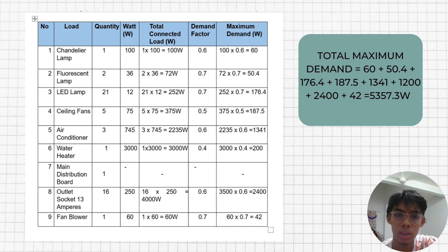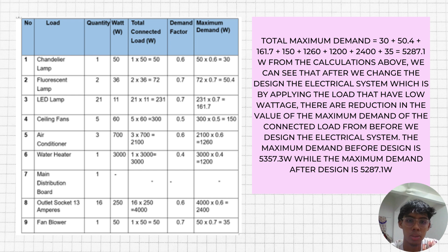After the design, we changed the chandelier lamp, LED, ceiling fan, and air conditioner wattage. After calculating the total load and maximum demand, we get 5287.1 watts. So the difference is about 70.1 watts in maximum demand.